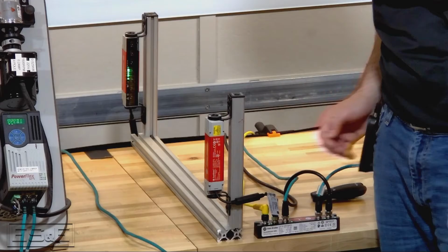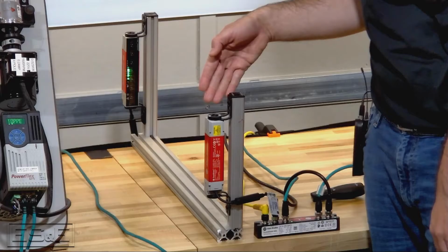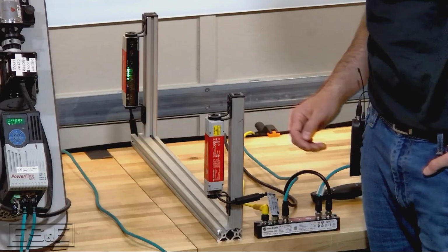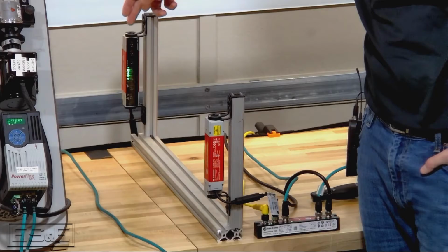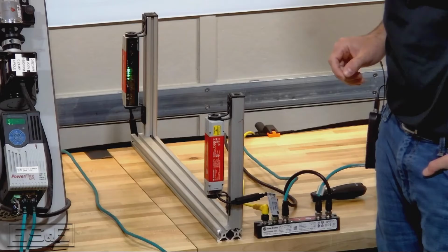And then also on the top of these light curtains, there's a synchronization beam. So if I break that synchronization beam, I'm going to lose communications entirely between the devices. So they actually use that synchronization beam to communicate with one another and verify that they're operating properly.